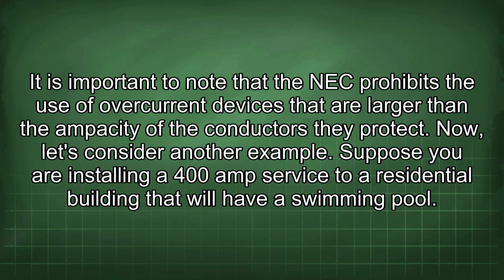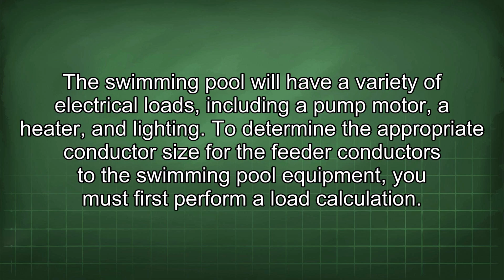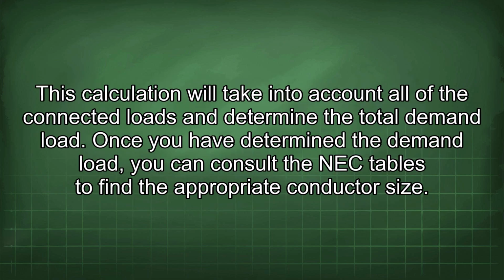Now let's consider another example. Suppose you are installing a 400 amp service to a residential building that will have a swimming pool. The swimming pool will have a variety of electrical loads, including a pump motor, a heater, and lighting. To determine the appropriate conductor size for the feeder conductors to the swimming pool equipment, you must first perform a load calculation. This calculation will take into account all of the connected loads and determine the total demand load. Once you have determined the demand load, you can consult the NEC tables to find the appropriate conductor size.